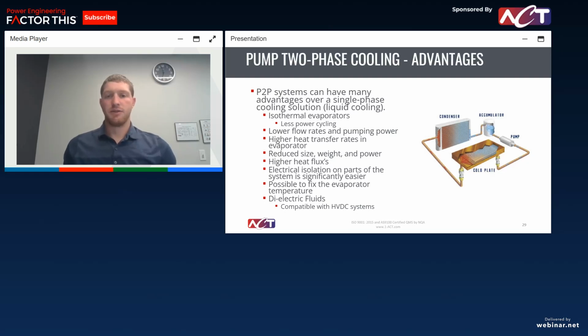Also, you're going to see a lot lower flow rates and pumping power, which lets you have a much smaller pump. Also going to be less power consumption. We've seen probably about 80% reduction in pumping power needed. So on a system that you might need 10 gallons per minute for a single phase to meet your cooling demands, you might only need to pump 2 gallons per minute for the same cooling for two-phase. And so that's going to lead to a much smaller pump, less weight, less space claim, and less power consumption. So a lot of advantages there.